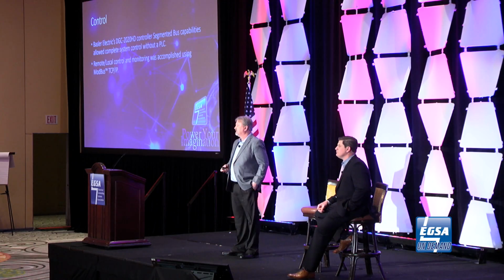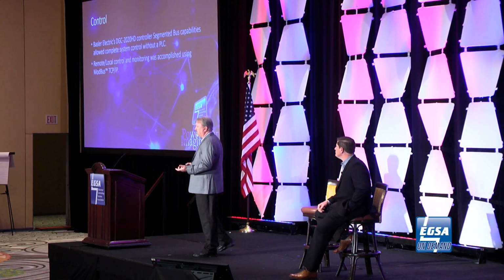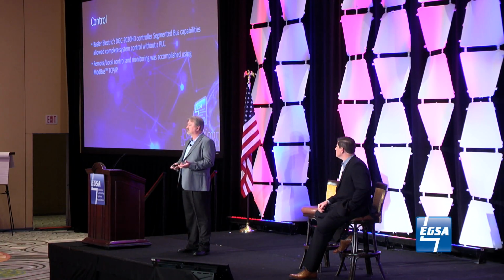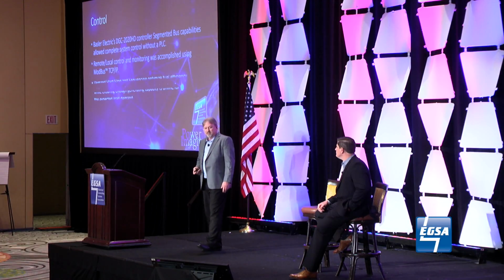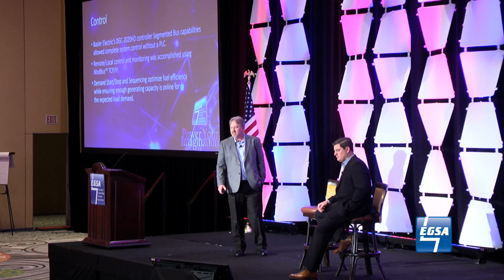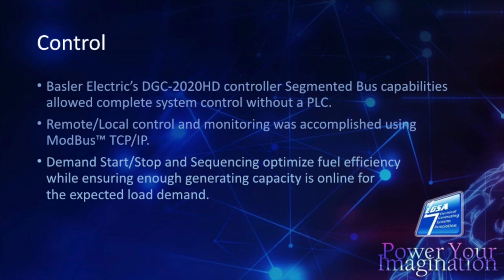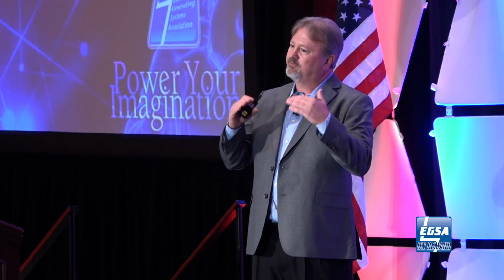It also enabled us to do remote and local control and monitoring over Modbus TCP. And that was a big advantage. We also set up the demand start and stop functions to optimize fuel efficiency and ensuring enough capacity is online. Now, since this was a new plant, we did have a couple of days where we had to do some testing, and load started while we were setting, we tried to set our demand spinning reserve as low as possible to optimize fuel efficiency, and that kind of bit us a couple of nights.